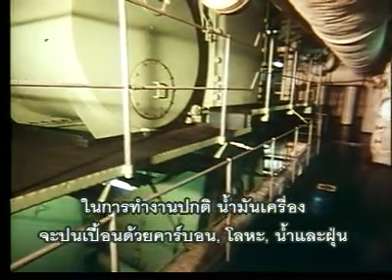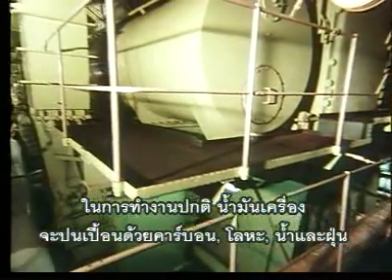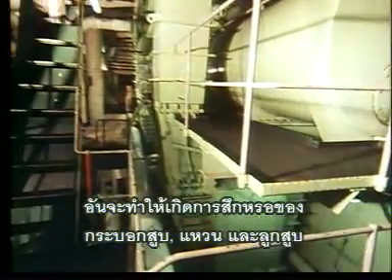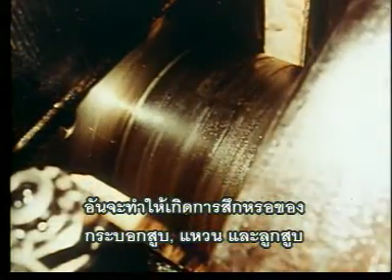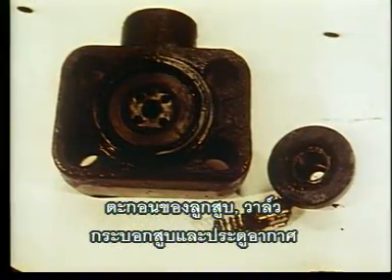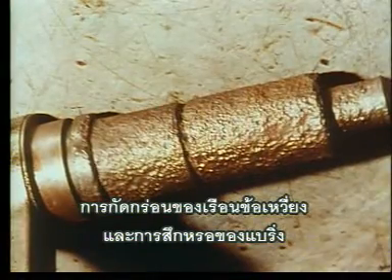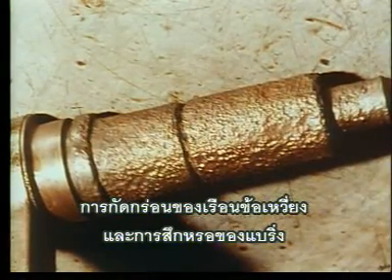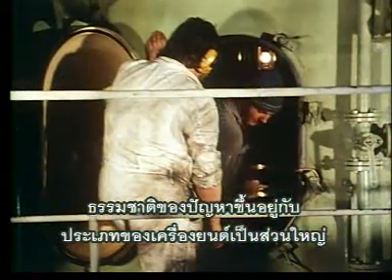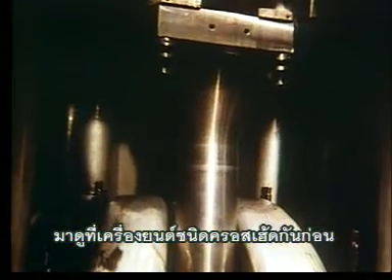During normal operations, the crankcase oils become contaminated by carbon, metal, water, and dirt. The following problems are caused: excessive wear of cylinders, rings, and pistons, excessive deposits on pistons, valves, cylinders, and ports, crankcase corrosion, and bearing failures. The exact nature of the problem depends largely on the type of engine. Let us look first at the crosshead type of engine.